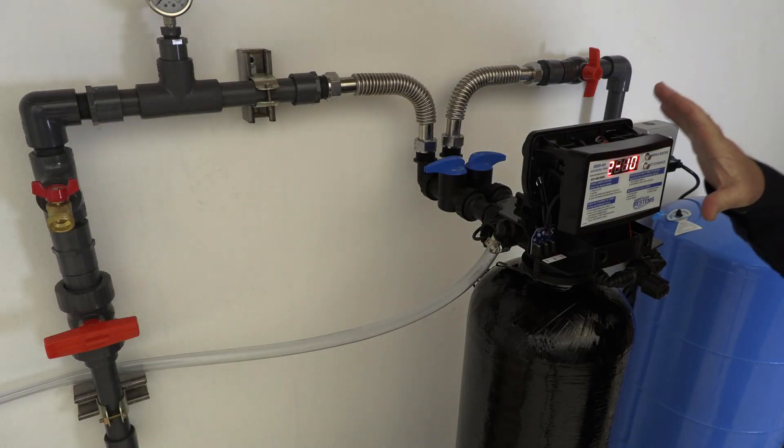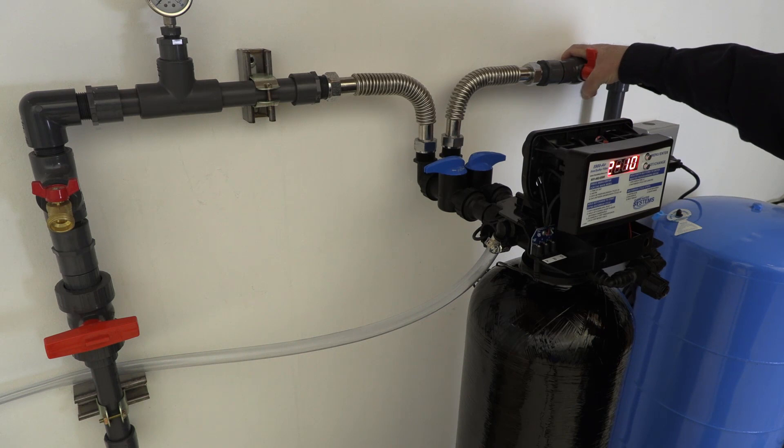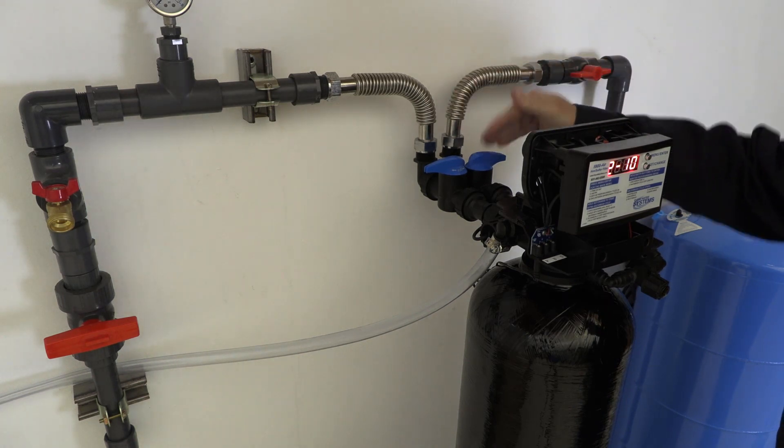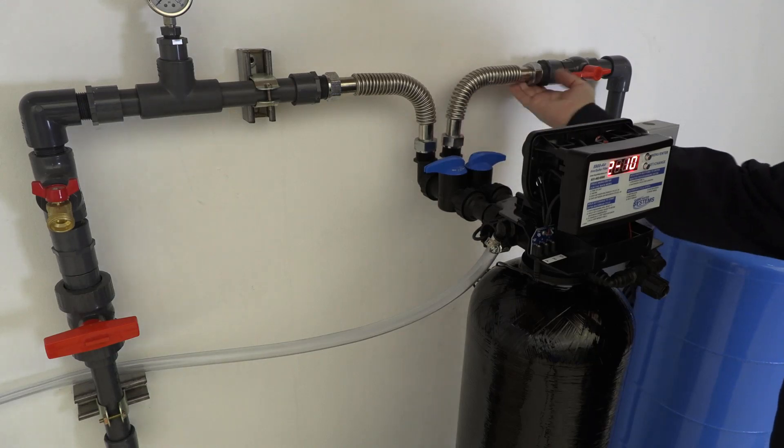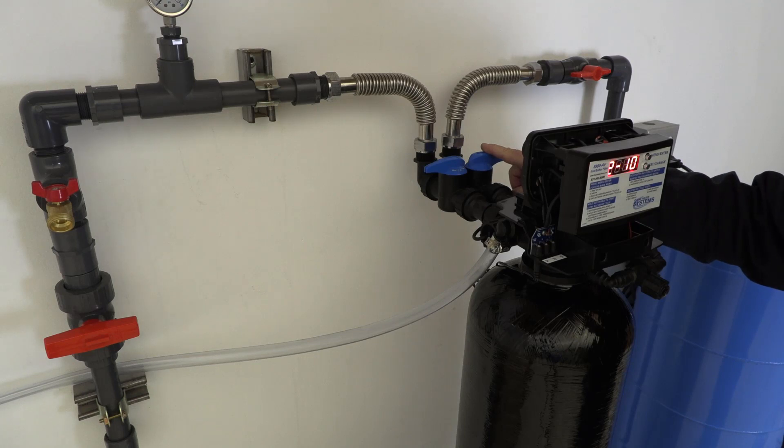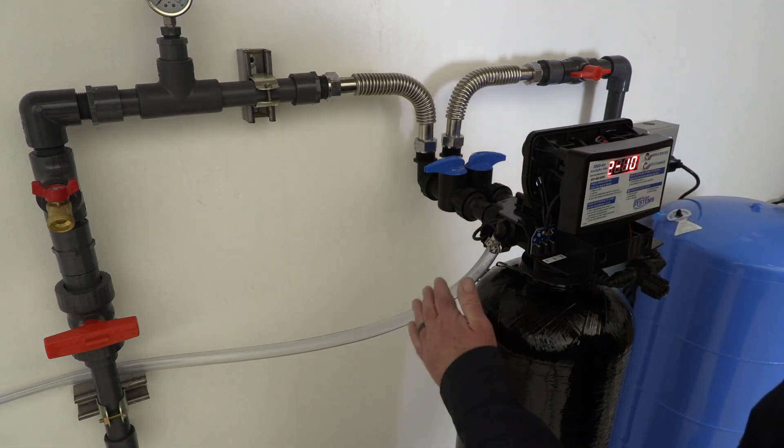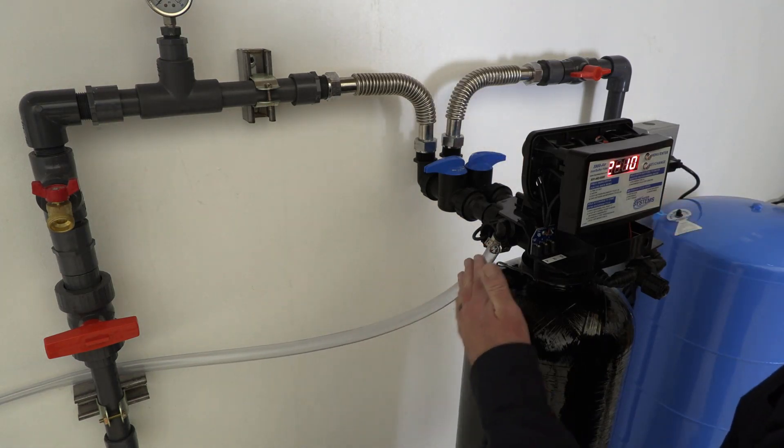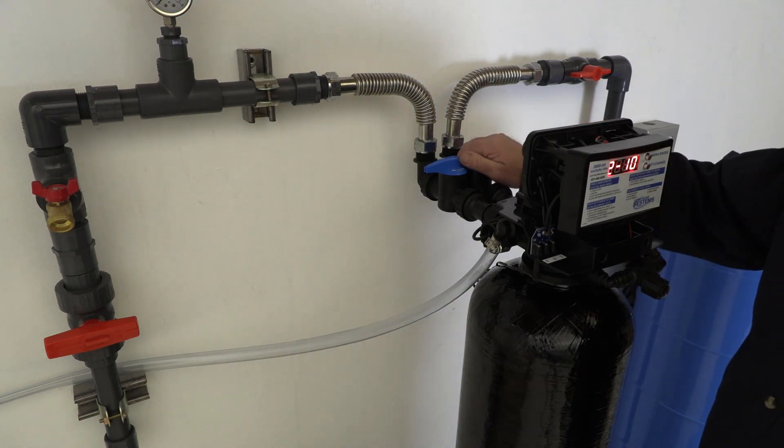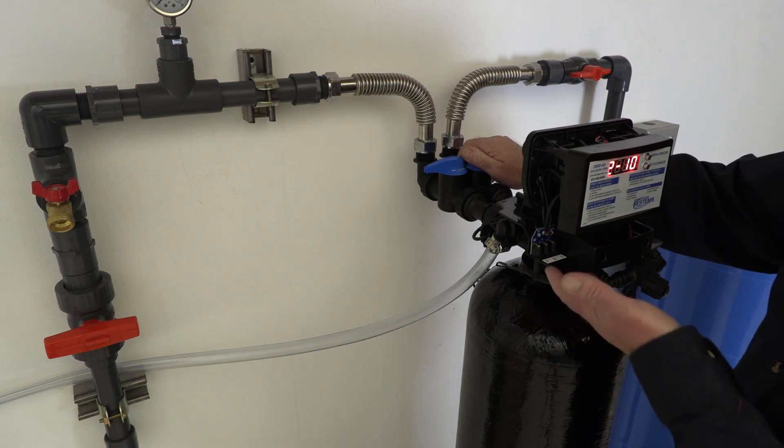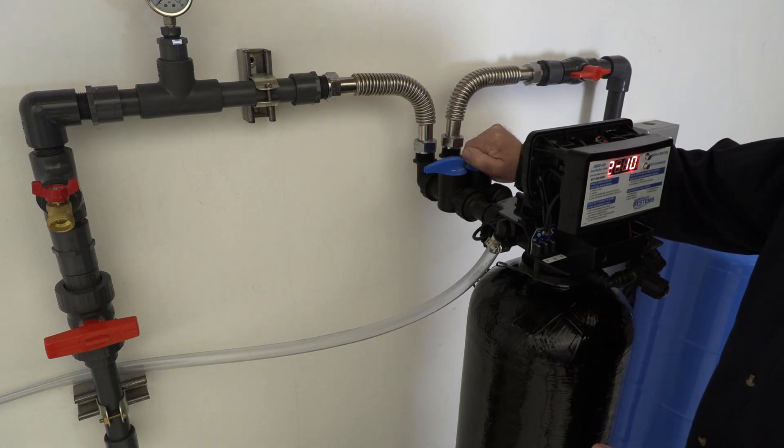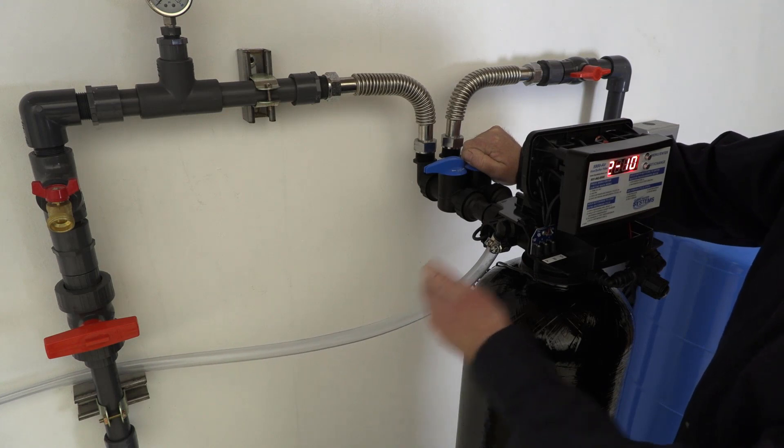So our valve is now in the backwash cycle. We're going to go ahead and bring our inlet pressure on, so now we have water pressure up to here. Leak check your fittings, make sure you don't have any leaks. We're going to slowly open the inlet valve on the bypass valve. What we're going to see is some aeration come out of the drain valve right here. What we want to do is do this very slowly—we don't want to blow the media back up into the valve head.